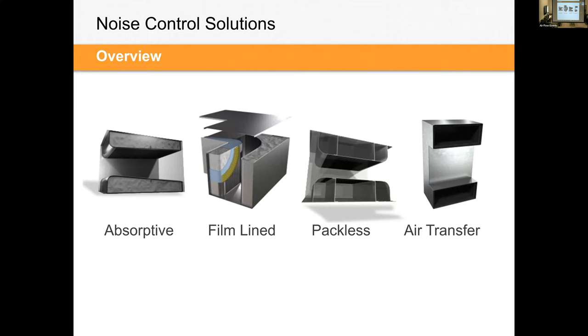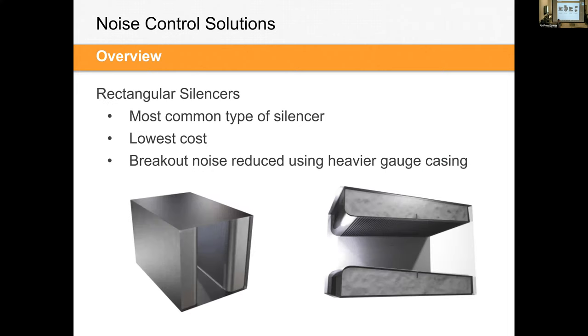Absorptive, film lined, packless, and air transfer are the main categories, and I'll talk a little more about each of these four, what they are and why they're important. Rectangular silencers are the most common practical type because a lot of commercial buildings use rectangular ductwork. They're quite simple, with no moving parts. It's basically perforated metal and acoustic media in baffles that absorb and attenuate the noise in a duct system.